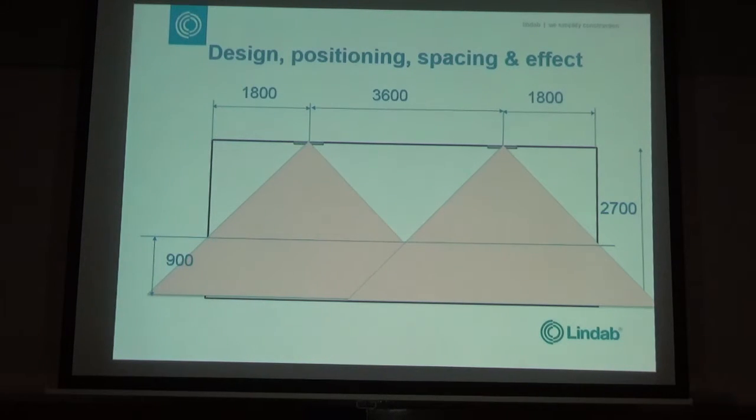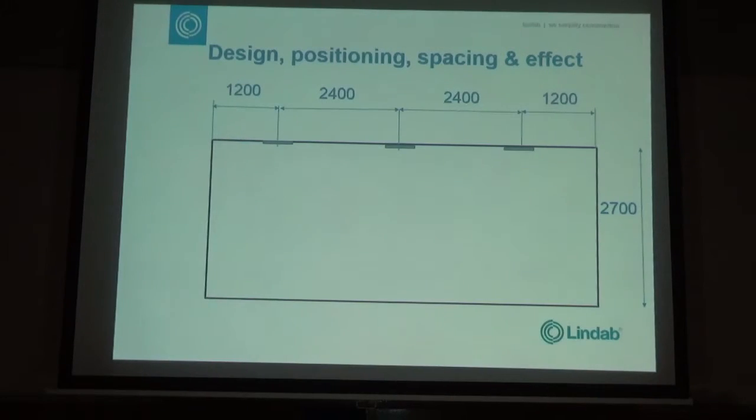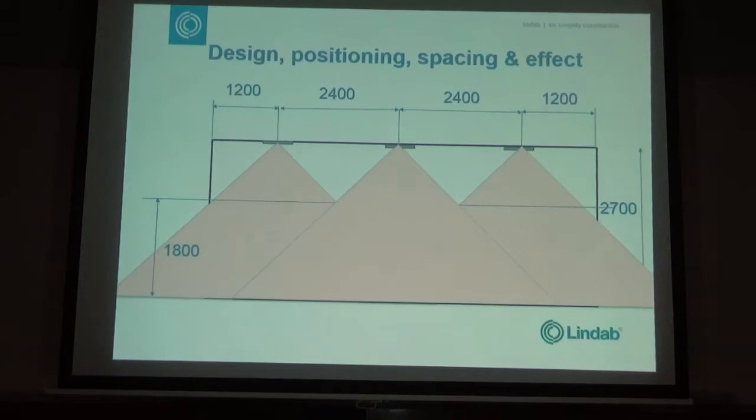So really what you should do, guys, with all apologies, this is what people want to pay for. So we're a bit cold. But this really is what we should do. So three panels, and that gives us a mounting height of 1.8. It's not strictly true because it should be at 1.5, but it's closer, so it's going to come to here instead of down here. So that's going to be all comfortable. It means that students in the classroom sitting along this cold wall, or with their backs to it, aren't going to be so cold.